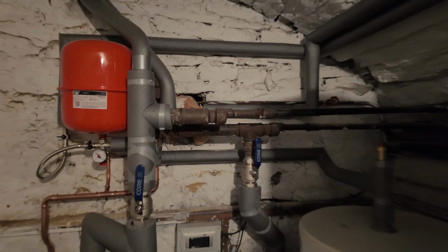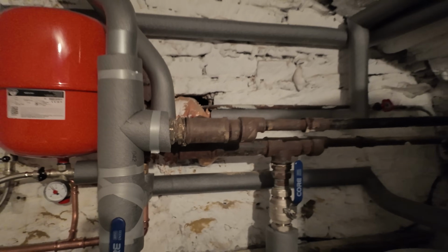Again, if you take a look at the existing heating pipe work, steel, okay, again, client didn't want to risk pressurising that, so what we did is we hydraulically separated it. True hydraulic separation. We're not talking buffer tanks here, we're talking heat exchangers. So what we want to do with the heat pump is not lose any temperature along the way. So if we're flowing at 40 degrees, for instance, from the heat pump, we want to deliver that to the radiators. We don't want to lose any temperature along the way.